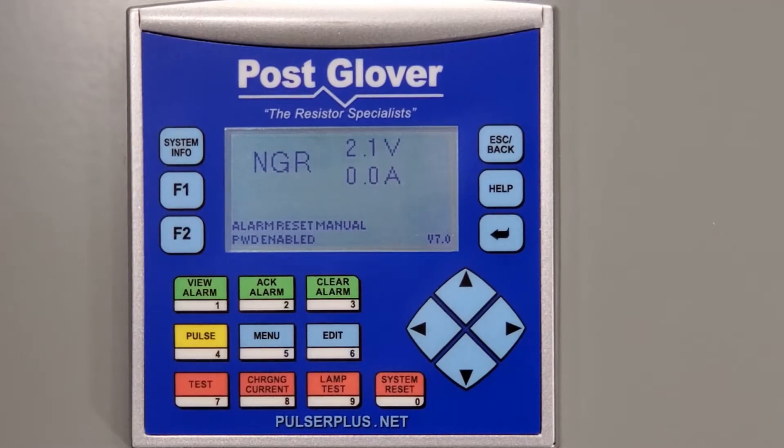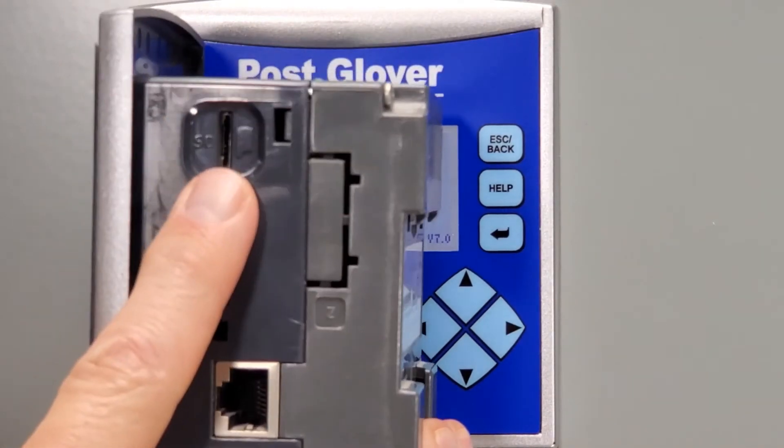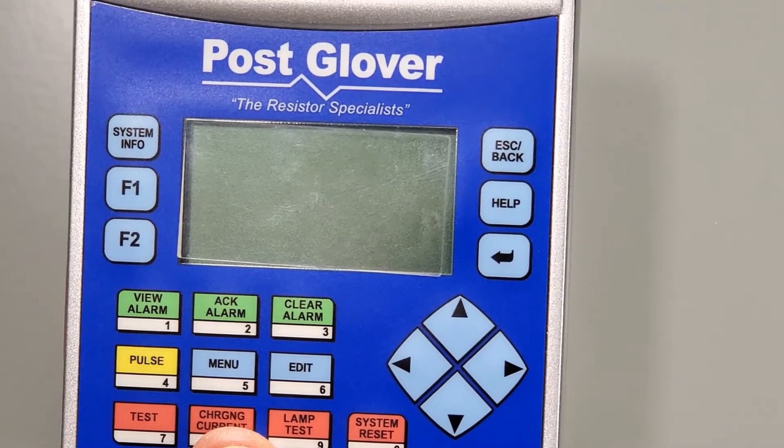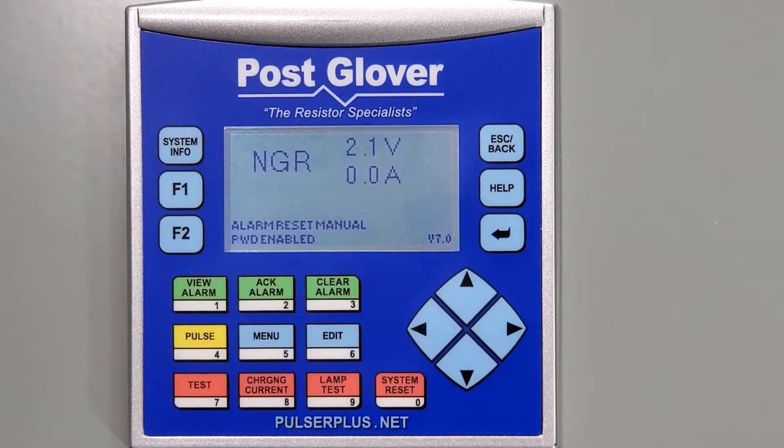This instructional video is generic for all of our PulserPlus .NET HRG systems dating back to about 2010. The latest version of the firmware can be sent to you by PostGlover either by email or we can send you a new SD card. The SD card is installed in the small slot on the PLC that's on the inside of the unit. Please note that you cannot change the name of this file or it will not load correctly. You will also need to note the name of the file so that you know which one to choose in case there are multiple versions on your SD card.